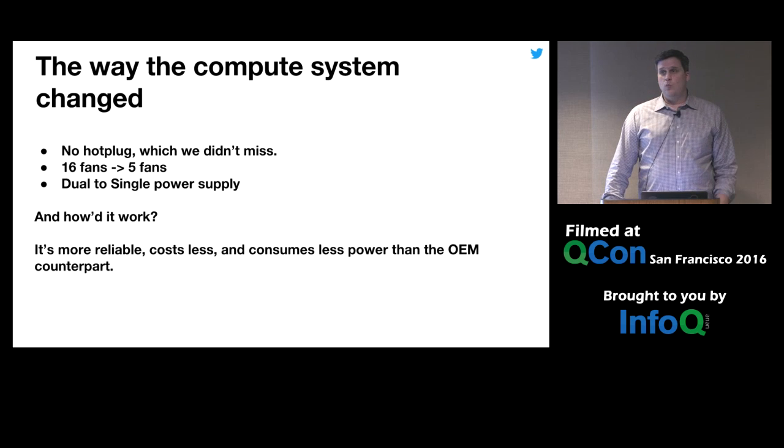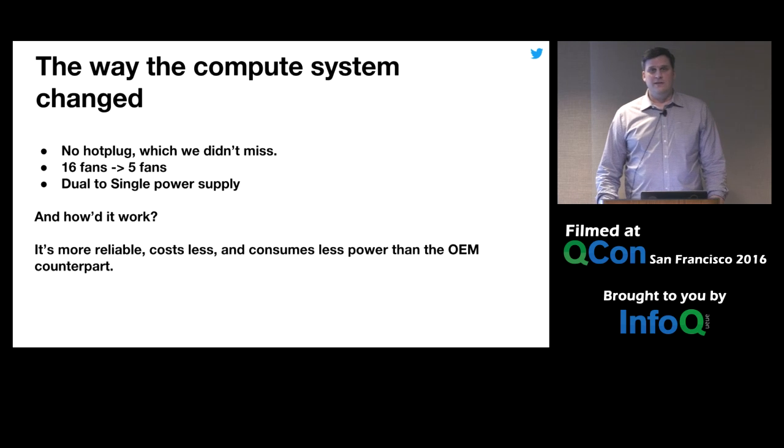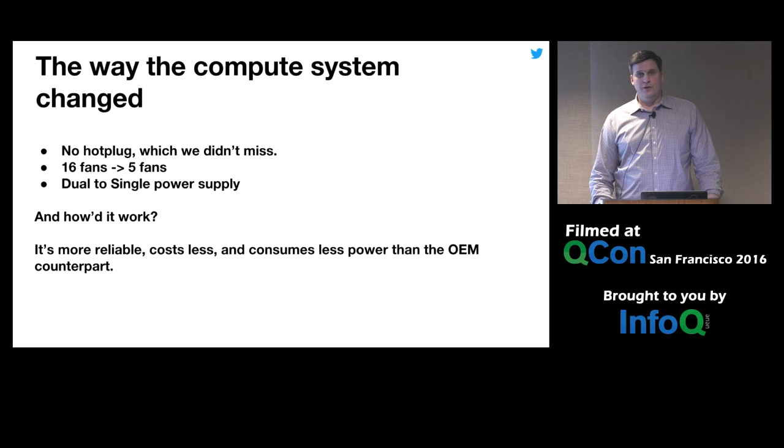These servers generally have 1 single boot drive in them. Hot plug was really not important. Going down from 16 to 5 fans, great power savings, really important in a data center when you're going to run these for years. And 5 fans fail less than 16 fans. And we went to a single power supply.